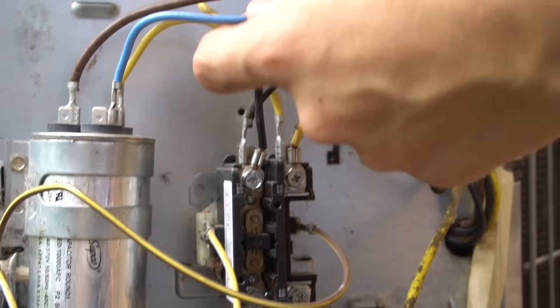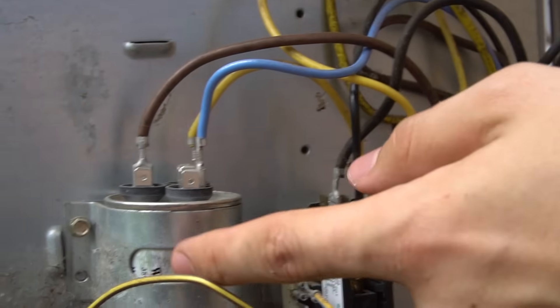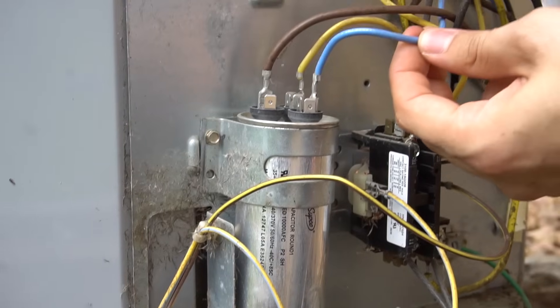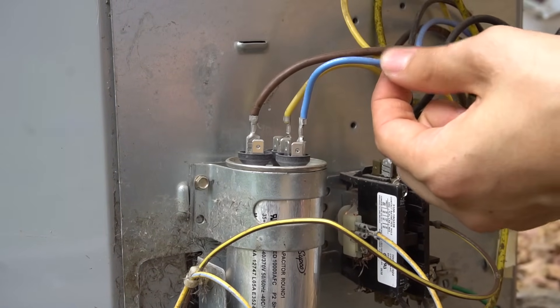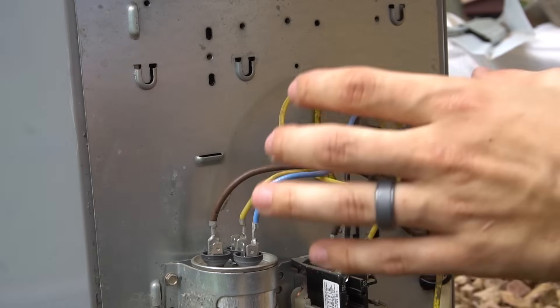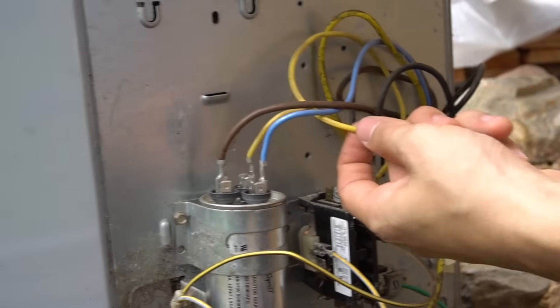And the last wire is going to go to the Herm section on your dual run capacitor. And many times the wire going to the capacitor will be blue, just like this one is on this unit. But different air conditioners will have different color wires.